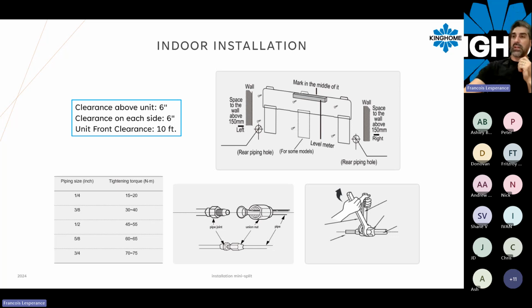For your indoor installation, same thing, we need some clearance all around the unit, about 6 inches. If you have less than 6 inches above the unit where the return air is proceeding, the system will work for sure, but the performance can be reduced. So the target here is always to have 6 inches. We can go maybe as low as 3 inches, but just keep in mind that the airflow and the overall performance of the system will be affected.